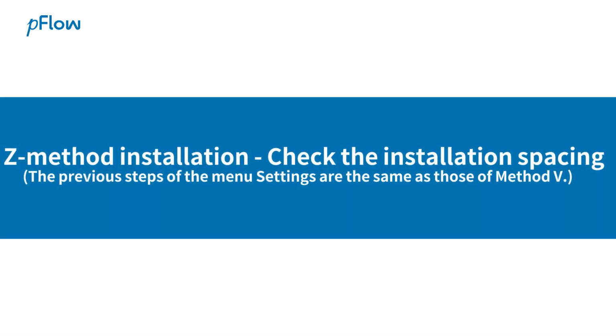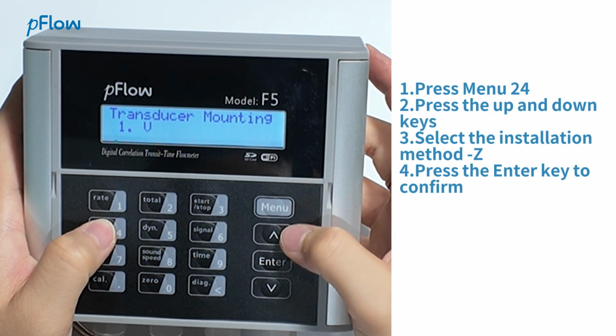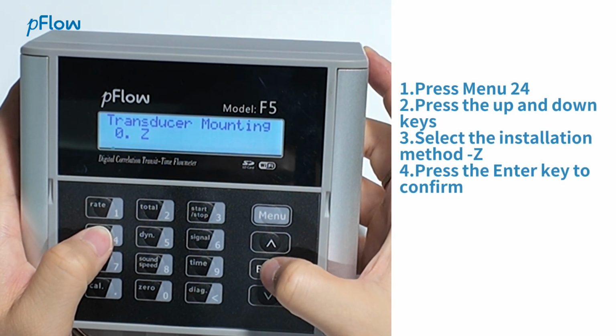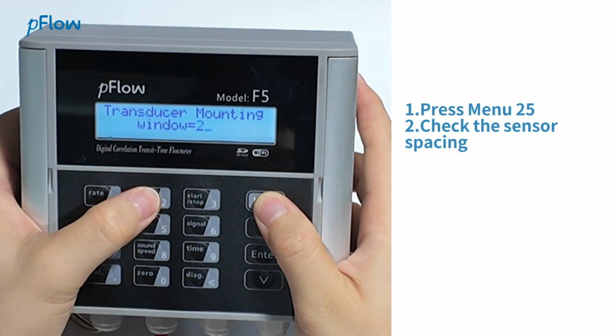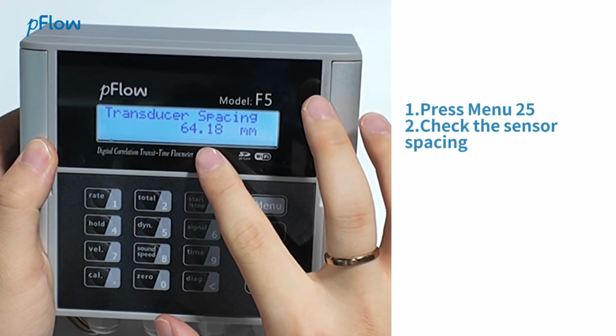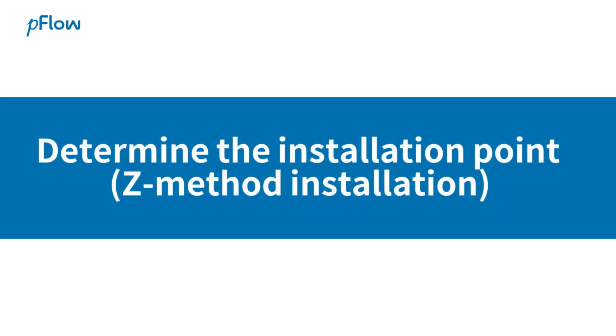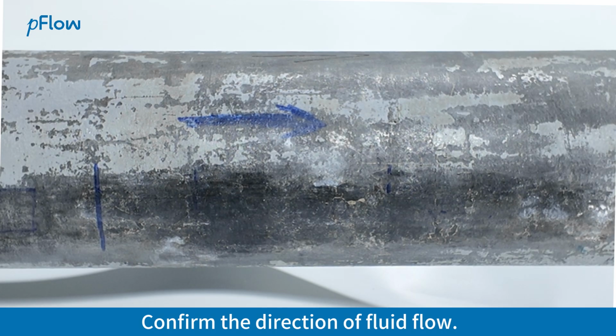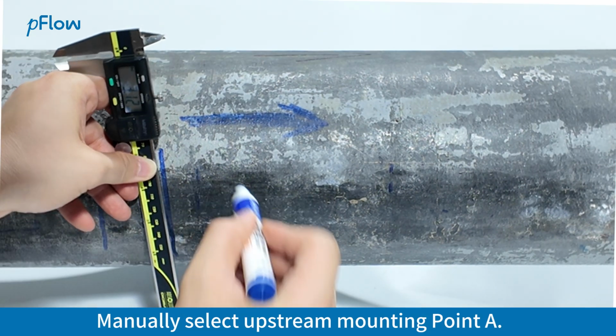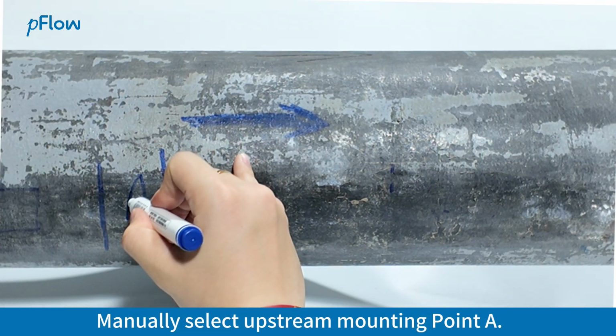Z method installation. Check the installation spacing. Select the mounting method in Windows M24. The transducer mounting spacing is auto-calculated and shown in Windows M25. Determine the installation point. Z method installation. Confirm the direction of fluid flow. Manually select upstream mounting point A.